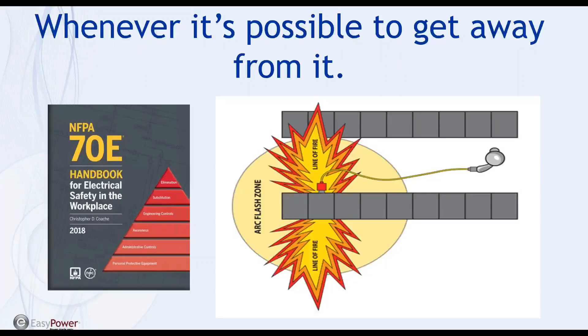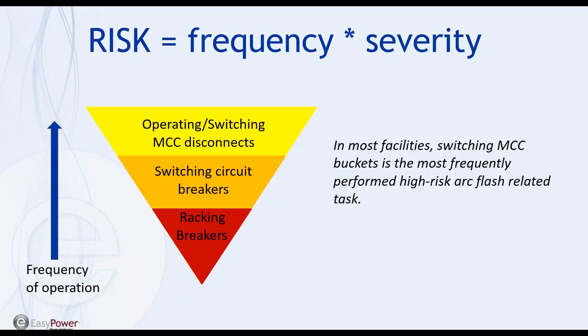This is a little chart we've used here at CBS ArcSafe before, and it points out the frequency with which you would do certain operations. Operating and switching MCC disconnects is the most frequent high-risk task in a lot of facilities, followed by switching of circuit breakers. In some places you may not rack a breaker but once or twice a year, if that. But as you go down that chart, the severity actually increases - the risk of a more severe incident. But regardless of what happens, what's important to remember is the incident energy at that particular unit is going to be the same. So we built our business really on remote racking in the early days. Now we're starting to see switching technologies and more customer demand for switching solutions - that's really been the next big wave for us.